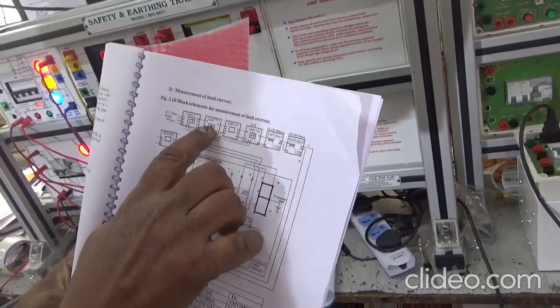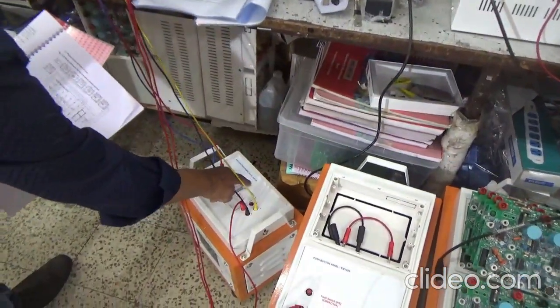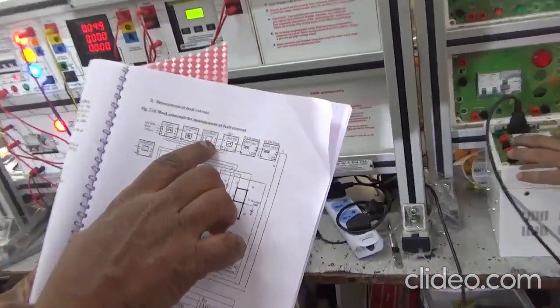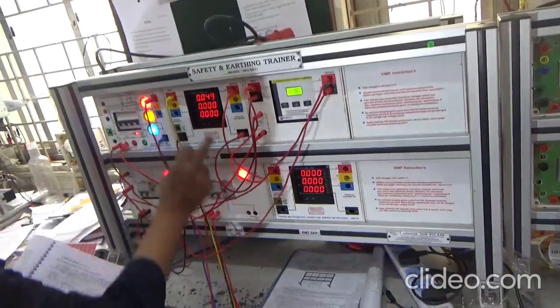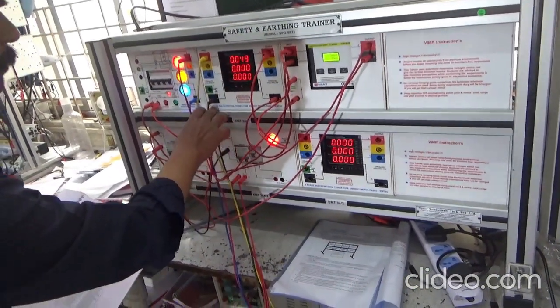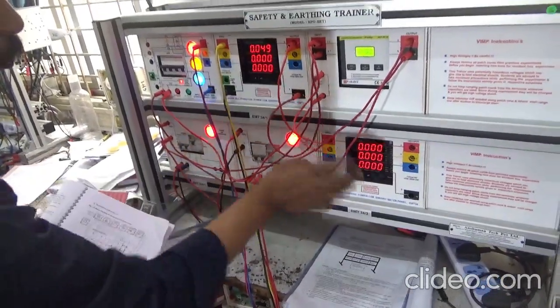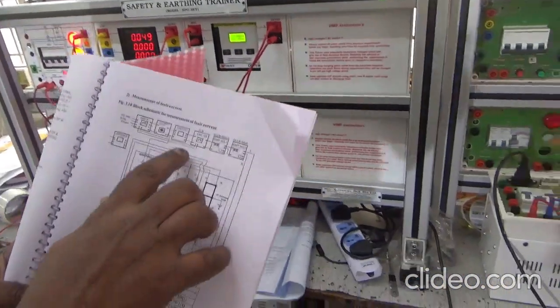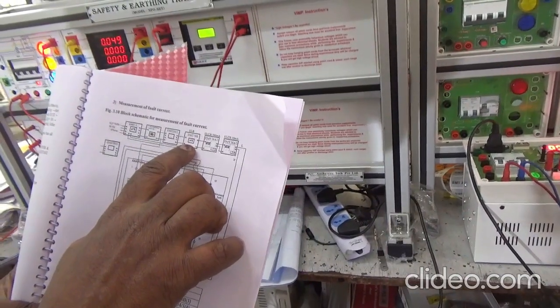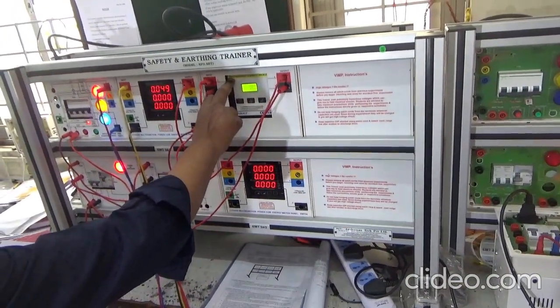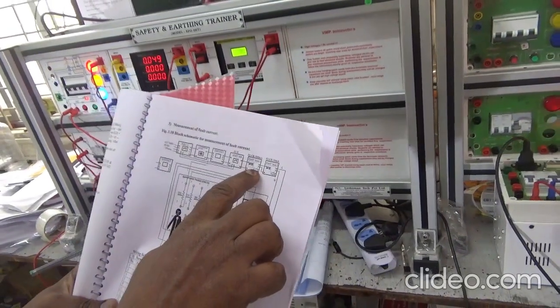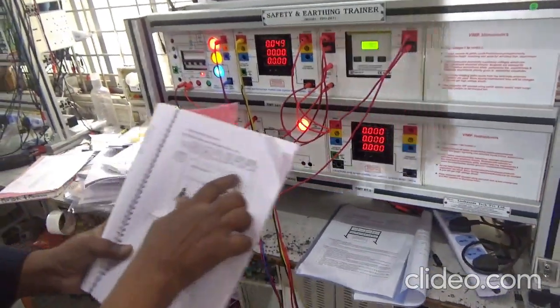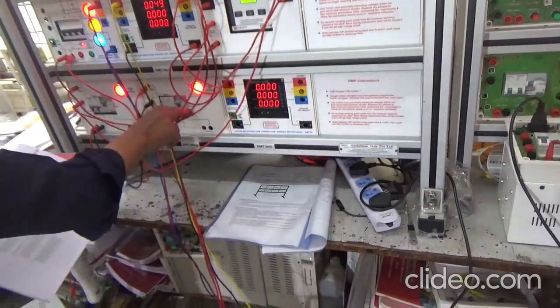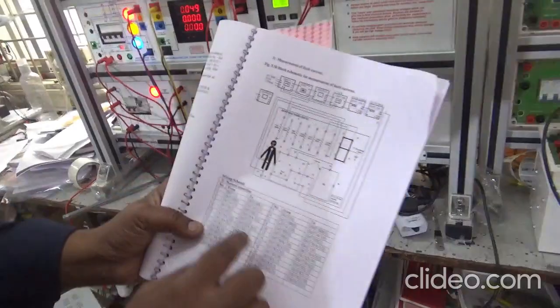The second one is the transformer. We have used an isolation transformer, 230 volt, 3 ampere, EMT18B. The next comes EMT34-1. So there are two EMT34s used. EMT34 means it is a multifunction power cum energy meter panel, 1 and 2. We have named it as 1 and here it is named as 2. Next is EMT50. So EMT50 is this one. This is the microcontroller based earth leakage relay. The next is ELCB 300 milliampere, and here it is ELCB 30 milliampere. This one is 30 milliampere. So two ELCBs, and in this way, this is the wiring schedule.